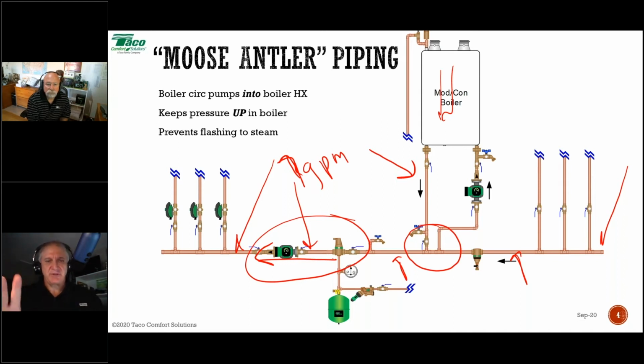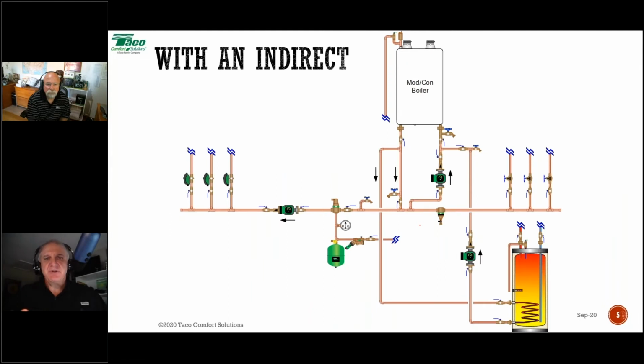All right, we'll talk about hydraulic separators in a minute, but I want to make sure this is cool. And I'm going to move on to the same basic piping arrangement, but with an indirect. You'll note when we take the indirect off of the unit here, we're taking it off of the boiler loop, and our supply comes off here at this point on the supply heading into that header. The return comes in after the boiler pump. What happens is when we go into domestic hot water priority, this pump is off. All right, that pump turns off.